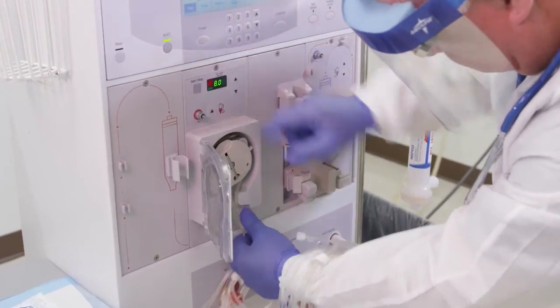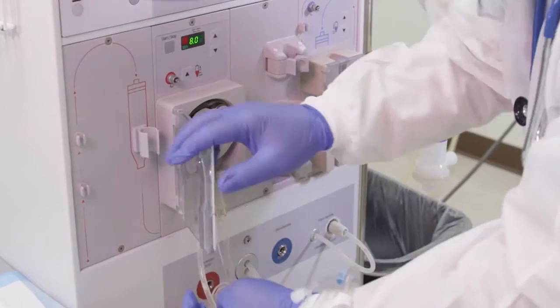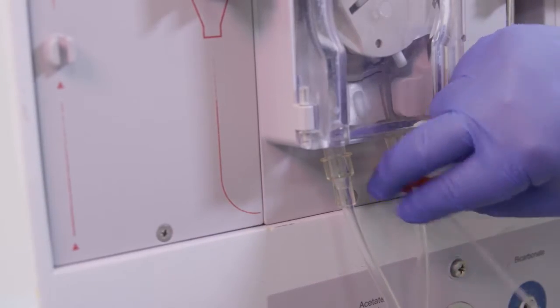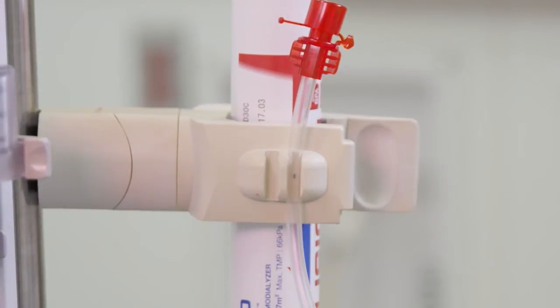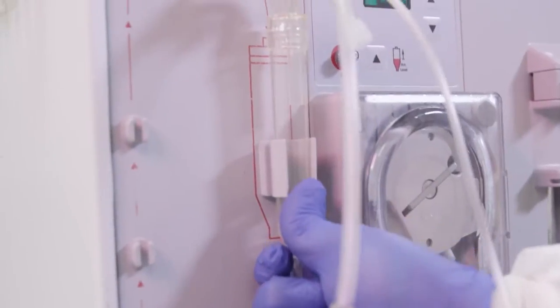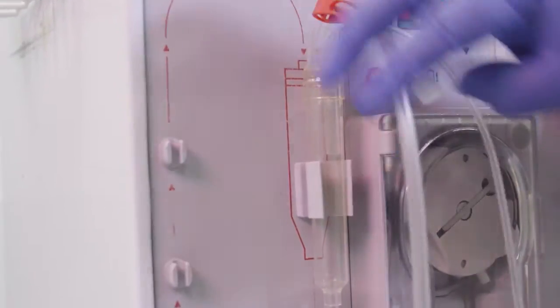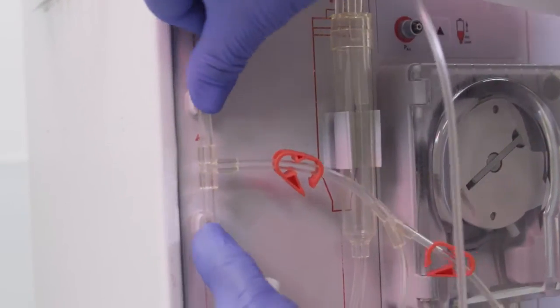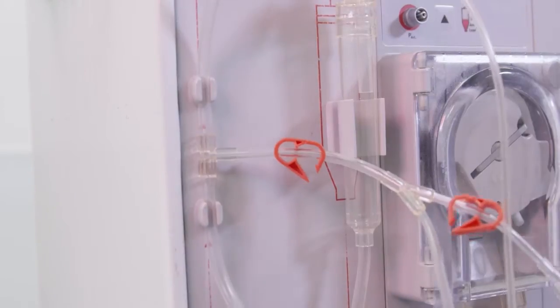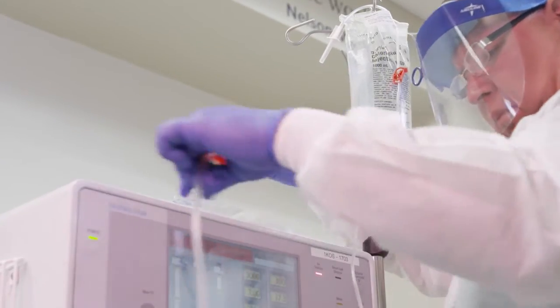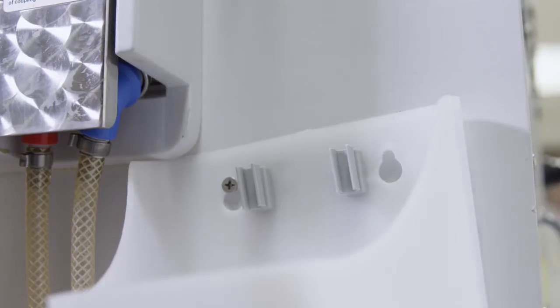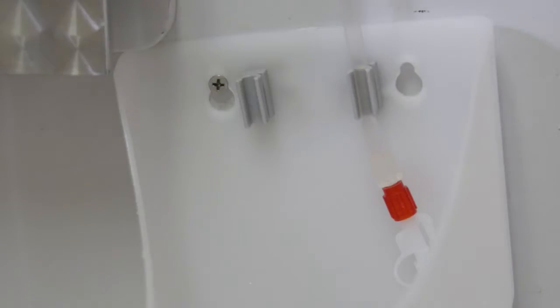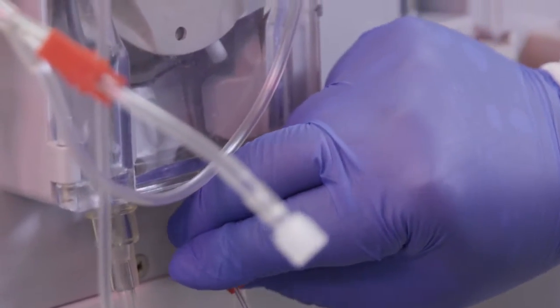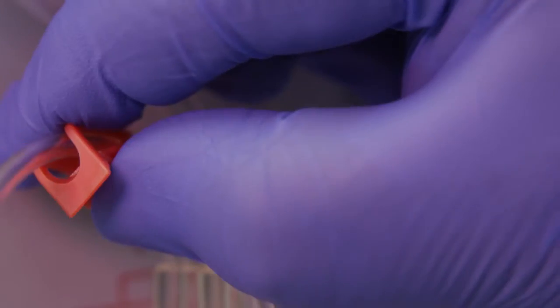Thread the arterial blood line through the blood pump and clamp the heparin administration line as close to the blood line as possible. Place the dialyzer end of the arterial blood line into the appropriate groove or clip on the dialyzer holder. Attach the arterial drip chamber. Attach the saline tee. This has the permanently attached priming set. Place the patient end of the blood line into the priming container, verifying that the end of the line does not come in contact with the container. Close all small clamps on the arterial blood line, except for the saline infusion line.